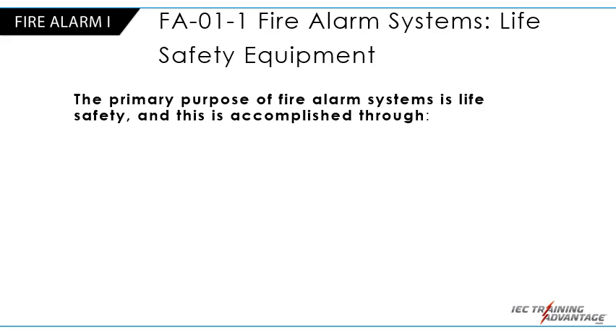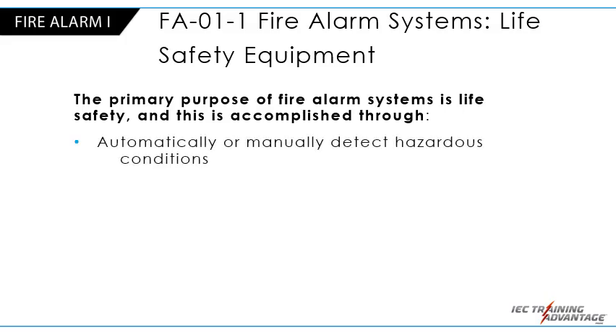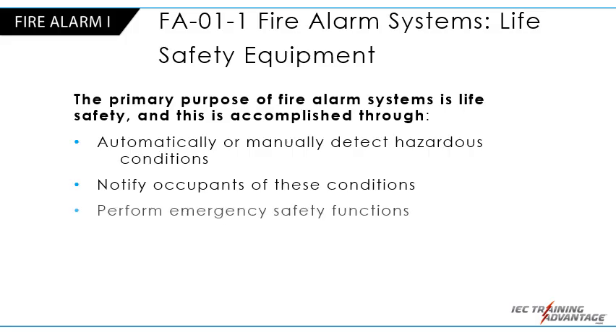FA-01-1, Fire Alarm Systems Life Safety Equipment. The primary purpose of a fire alarm system or fire alarm systems is life safety, and this is accomplished through automatically or manually detecting hazardous conditions, notifying occupants of these conditions, performing emergency safety functions, and supervising other systems. Supervised systems include fire pumps, sprinklers, and special hazard systems.